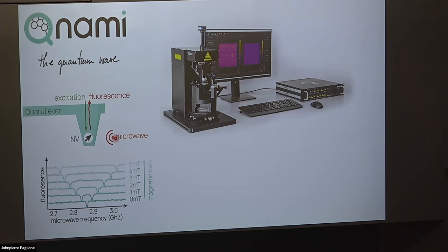And when they developed the optical, the cryogenics, Quantum Design already knew. Again, I didn't help develop it, I'm telling you the lore that I've been told, right? This has been passed down for generations. We know the cryogenics very well. We know how to make magnets pretty well, but that was a challenging magnet for us to make, a split coil magnet, especially conduction cooled, because you got to make sure that thing is completely cold and well synced to the cryo cooler. And then the third part of that was the vibrations.